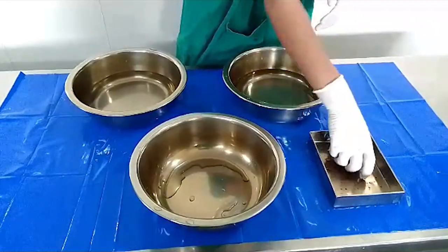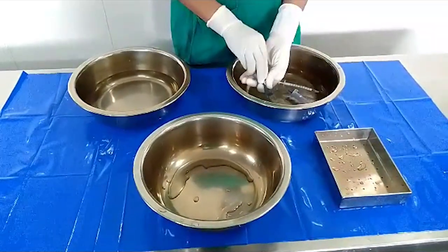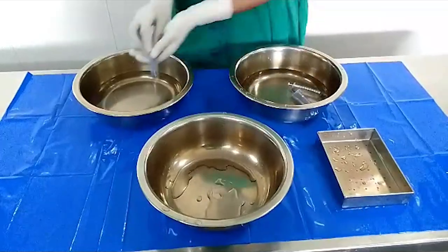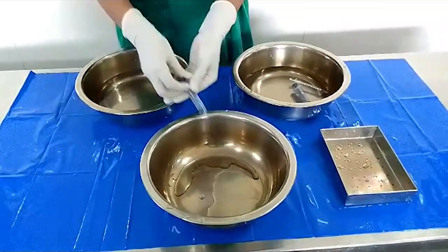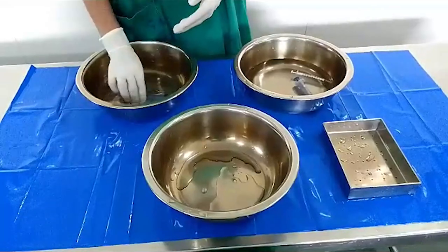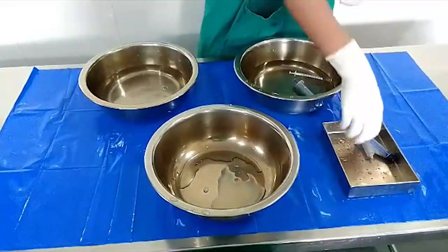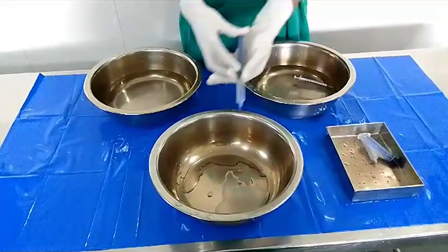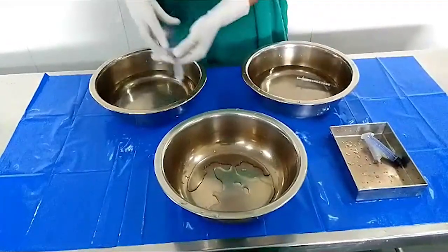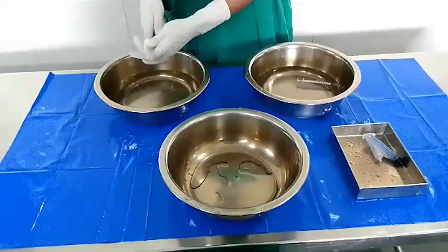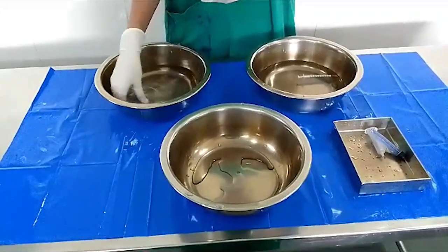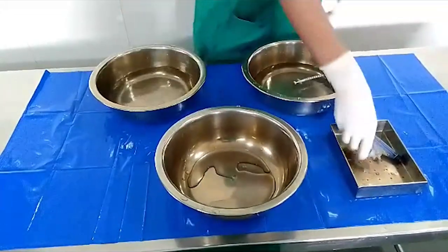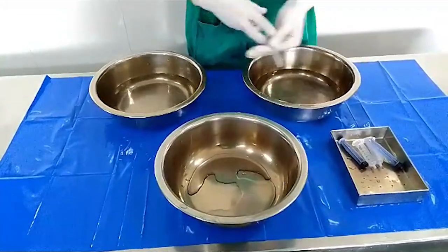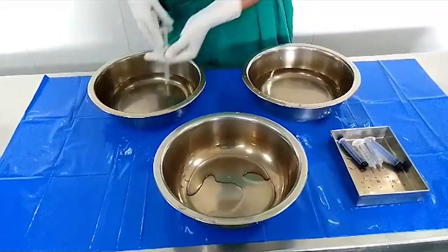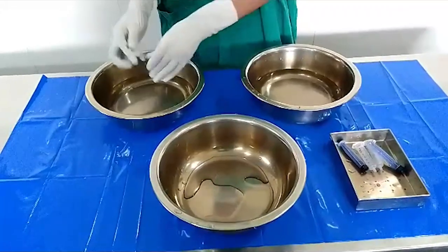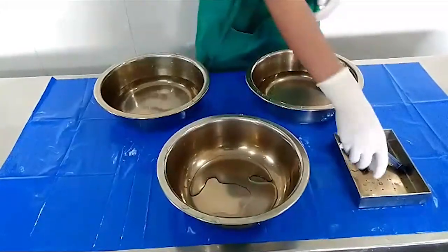So here we can see that we have 3 basins, 2 basins filled with RO filter water and 1 empty basin. So the syringe is filled with RO filter water from the second basin and emptied into the third one, and again filled with RO filter water in the first basin and then from the second basin and then emptied into the empty basin. This procedure is done for all the 2 cc and the 5 cc syringes. Separate it from the plunger and send it for sterilization.